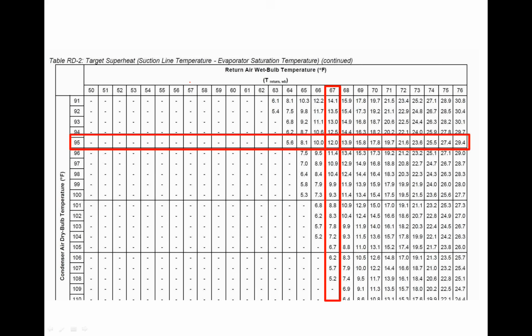This is a simple target superheat chart, but you can see here, this is a condenser dry air entering temp on the left, right? This little line right here is condenser dry bulb entering temp. So I have it highlighted here at 95 degrees outdoor air temperature. And if I take that across till I correspond to a 67-degree wet bulb, you can see right here in the middle, it corresponds to 12 degrees of target superheat. So under the ARI design conditions, 95 and 67, that system would be exactly 12 degrees of superheat. That's the typical target superheat. And that whole chart is sort of derived from this, okay? So, and I'll show you a little bit how this works in just a second, but I just wanted to show you, when we talk about 12 degrees being target superheat or typical superheat, that's where it came from.